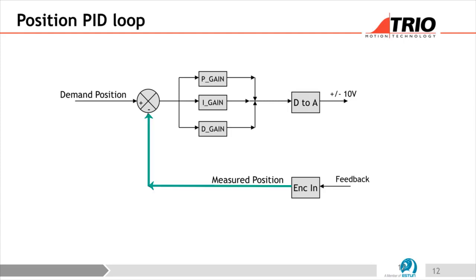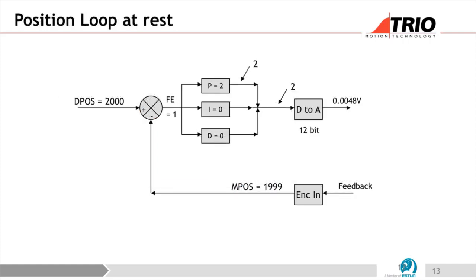Inside the controller we want to control the position of the motor, so we take that feedback information and compare it with our required position. We then output a voltage to tell the motor which way to go, since that voltage is proportional to speed — 5 volts gives 50% of full speed. For a 3,000 RPM motor, 10 volts is 3,000 RPM. The feedback from an incremental or absolute encoder becomes what we call the measured position, which gets compared and goes through a typical PID control loop.